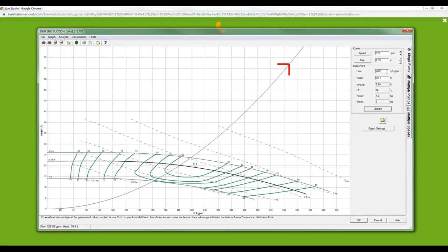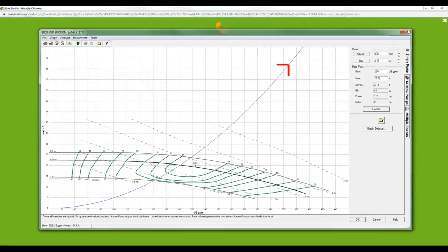At 200 gallons per minute, I'm only now at 20 feet of head. And what happened to my power? 1.2 horsepower. I really reduced my power. Just to review.